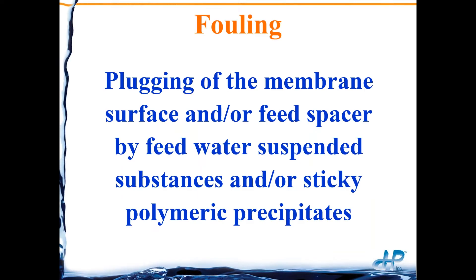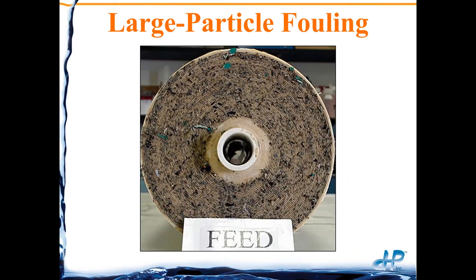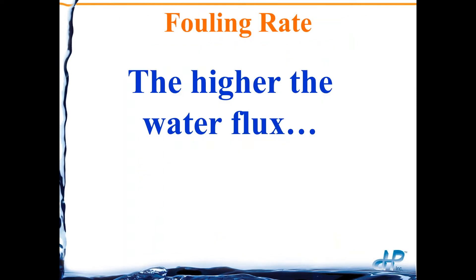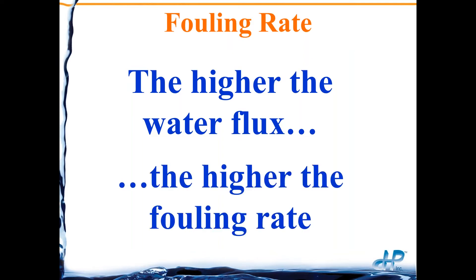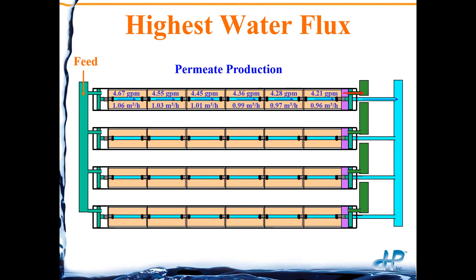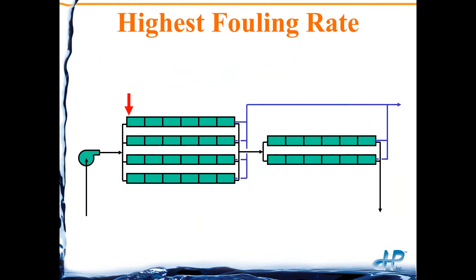Two problems we're going to talk about are fouling and scaling. Fouling is plugging of the membrane or feed channels by particles or sticky polymeric precipitates. The fouling rate is highest where you have the highest water flux — the highest permeate production — which occurs right at the very front of each pressure vessel. So the highest fouling rate is in the first inch or centimeter of the first membrane element in a traditional RO unit.